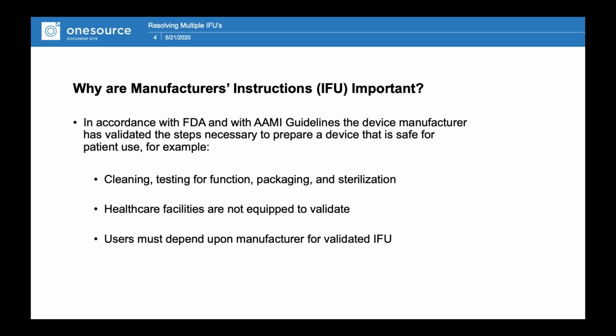Now, within that booklet, like I mentioned, the SPD folks may get that booklet. And what we tend to do is we skip to the back of the booklet because we're looking for the sterilization. In the more recent past, it was all about the exposure time. How long do I need to sterilize this device? Typically, in the past, our standard cycles were 4 minutes of exposure, but now we have these extended cycles. So we would jump to the conclusion of the book, if you will, and look for that sterilization time.